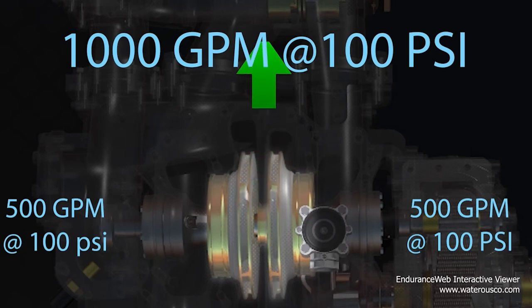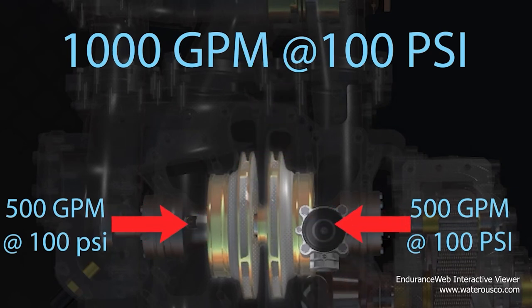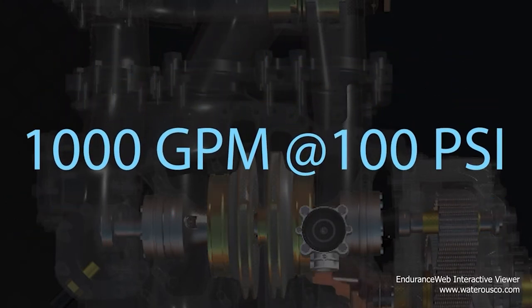In volume mode, the impellers work independently to produce maximum flow. Both impellers increase the velocity and pressure of water at the same time, doubling the amount of water at the same pressure.